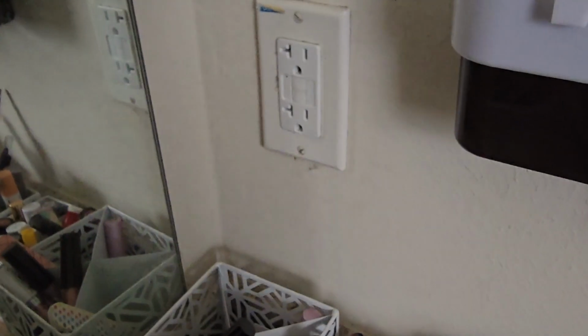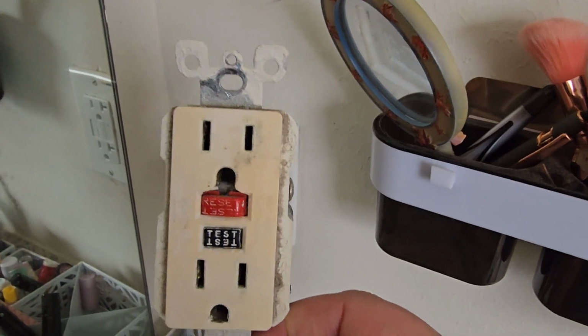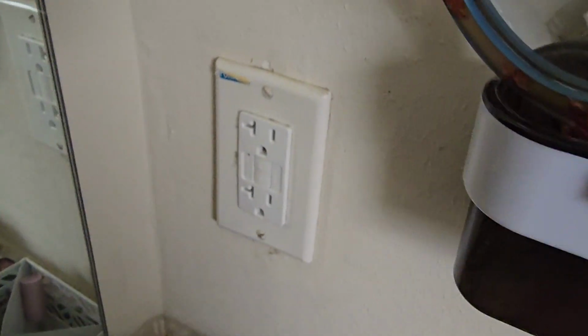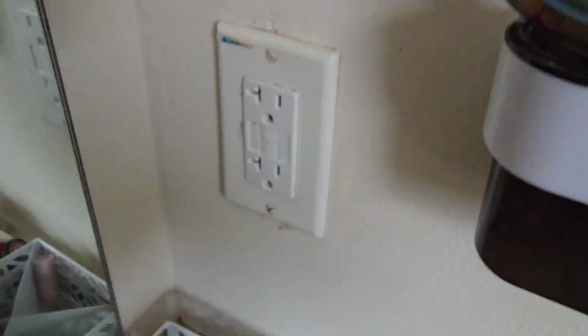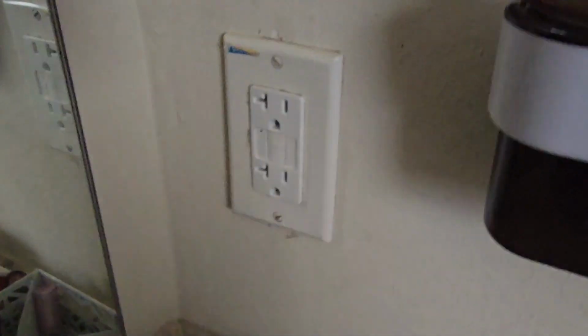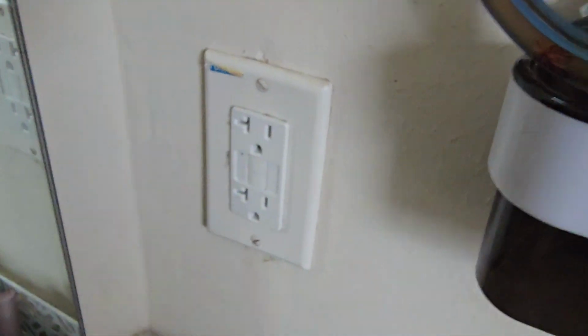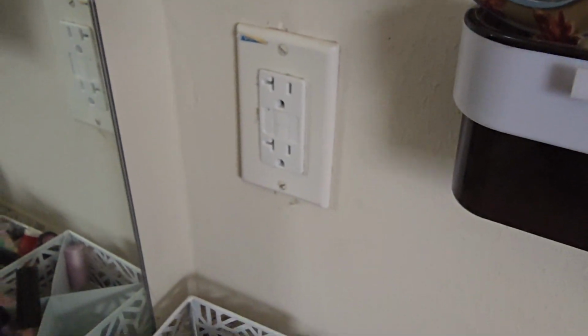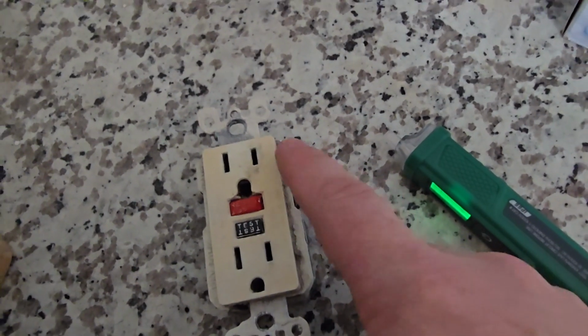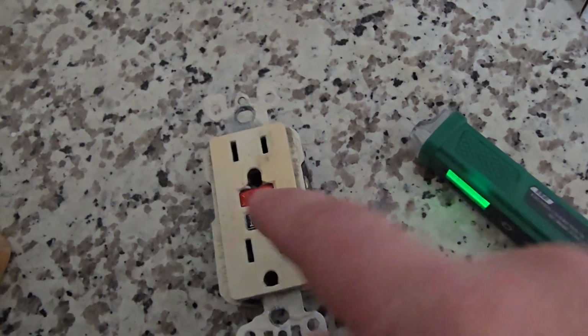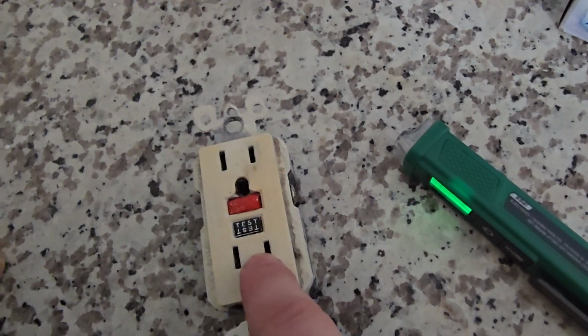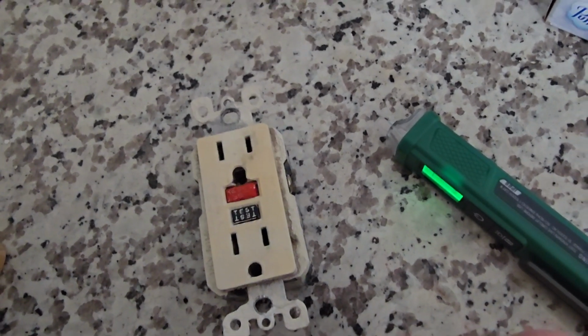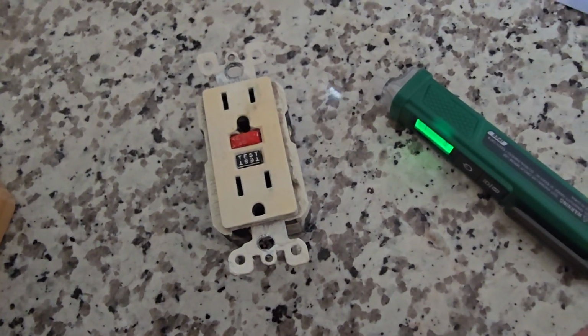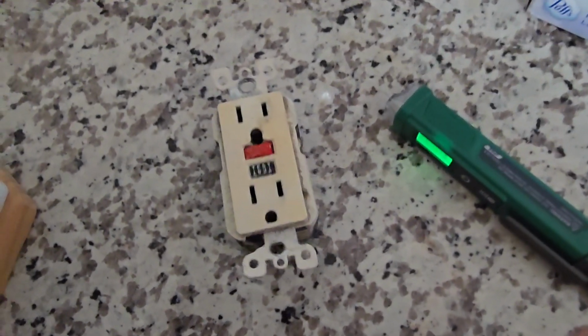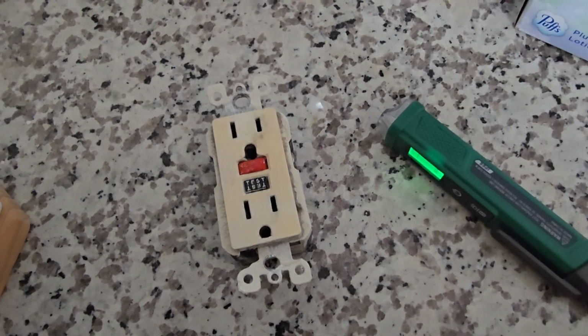I had power clearly coming in, but when I checked from hot to neutral, I had 0 volts. When I checked from hot to ground, I had 120 volts. Interesting. On this one, I have 120 volts, and across these two here, I got 0 volts, and across these two, 0 volts. So that means I lost a neutral. Interestingly, I lost a neutral. Now how the heck would I lose a neutral?